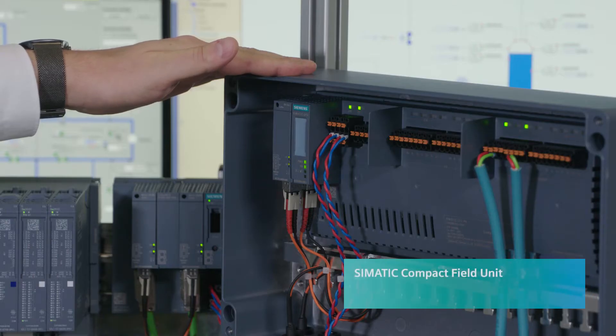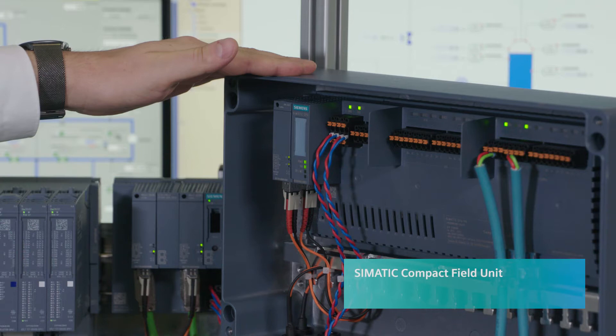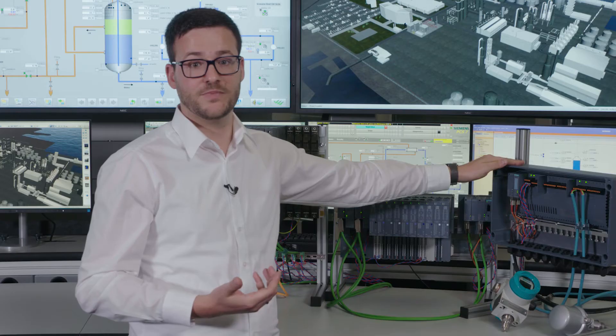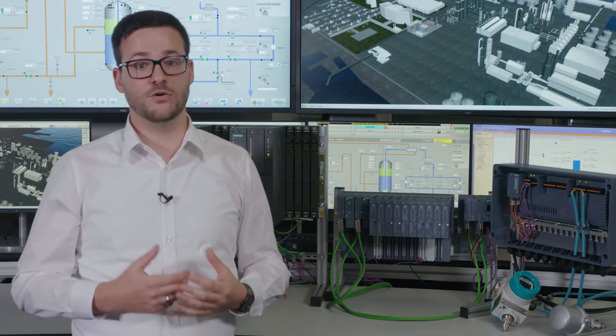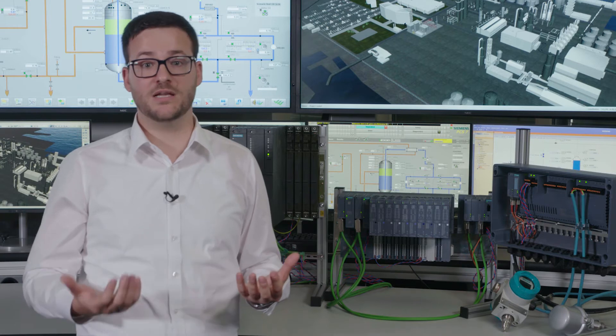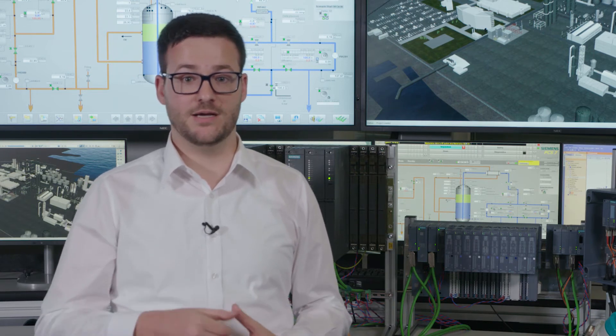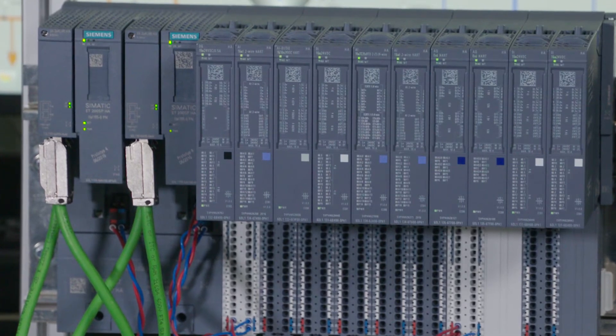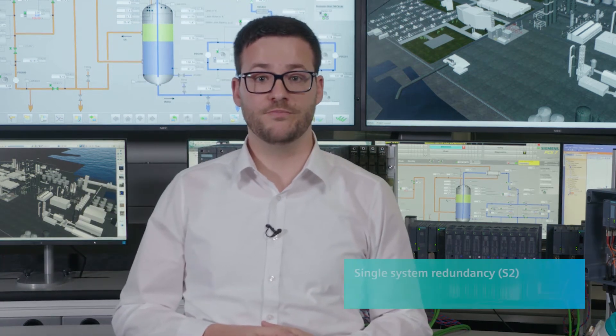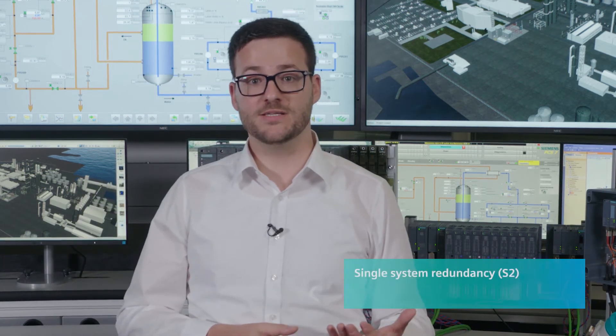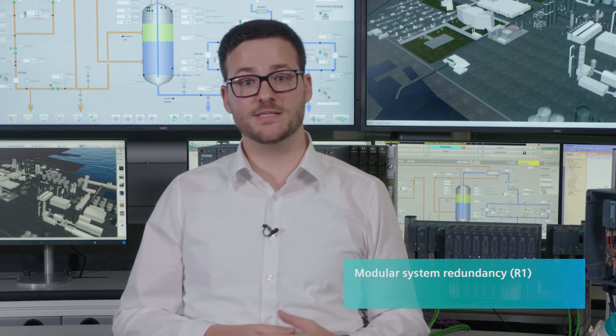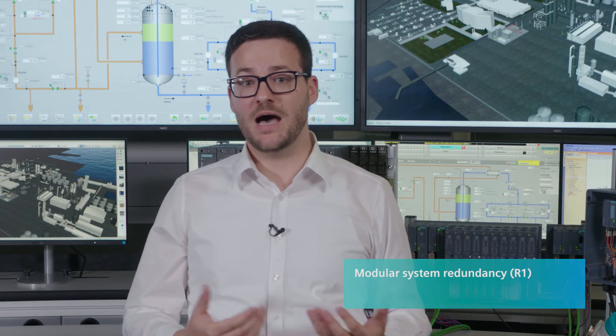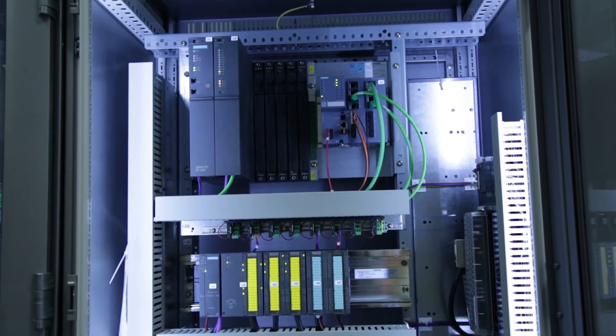Greater flexibility due to a consistent, decentralized approach and easier thanks to plug and produce. The new hardware components use bus adapter technology, which supports simple and flexible connection to the PROFINET network with either copper cables or fiber optic cables. PROFINET allows you to freely scale the availability of your plant based on your requirements. In addition to the media redundancy protocol MRP, two forms of system redundancy are available: Single system redundancy S2 and Modular system redundancy R1. What's special is that these can all be freely combined with each other.